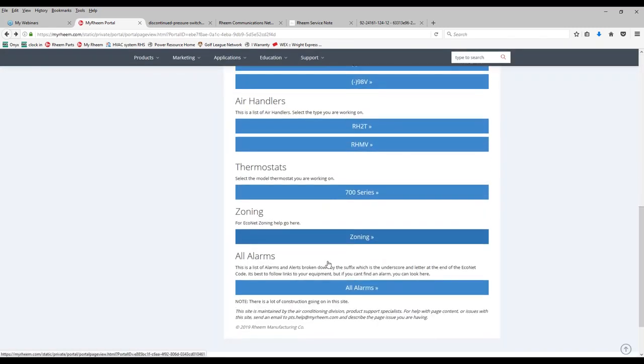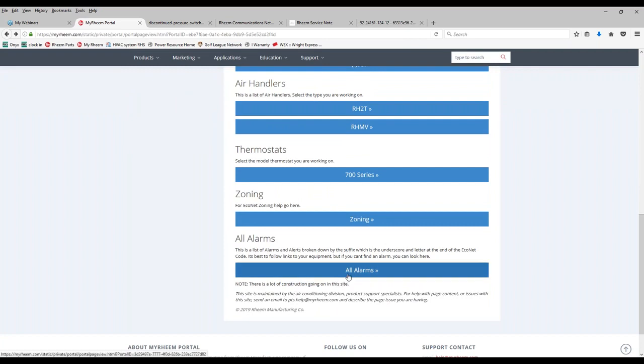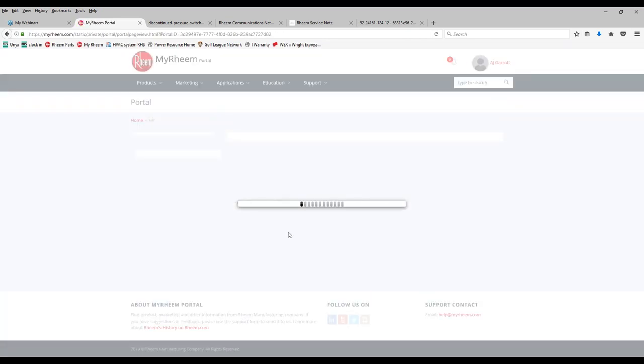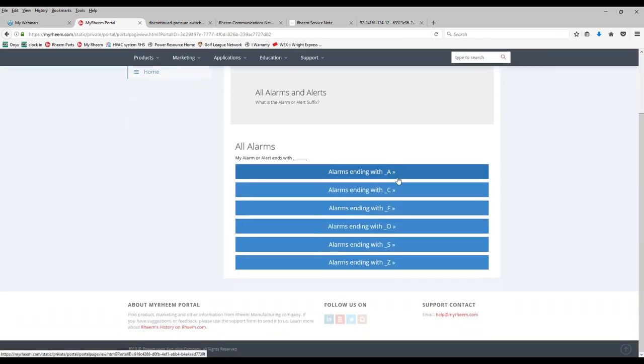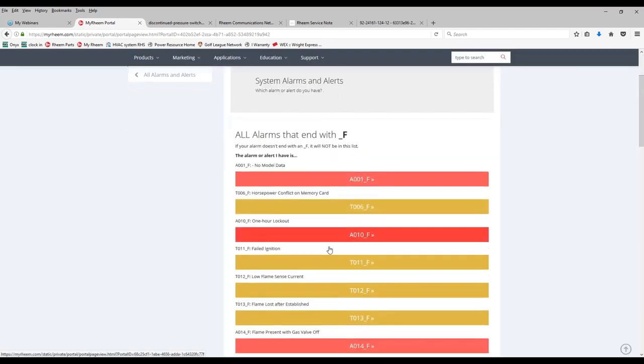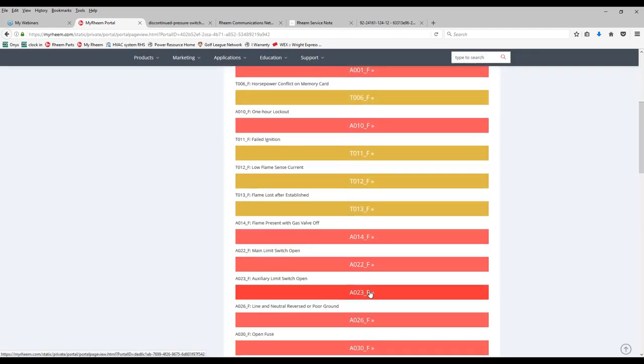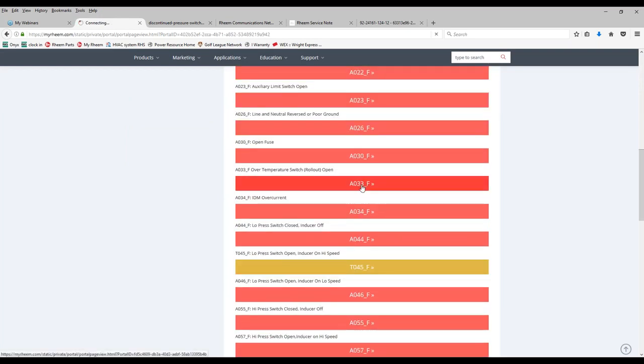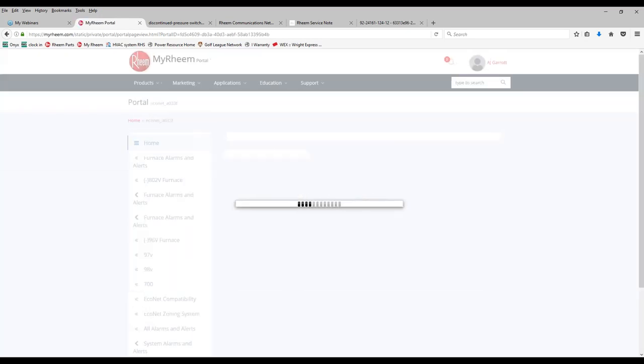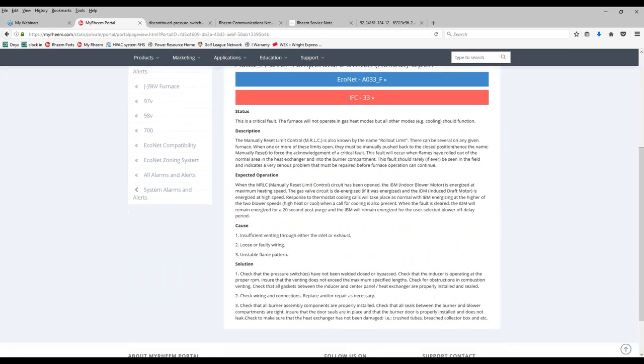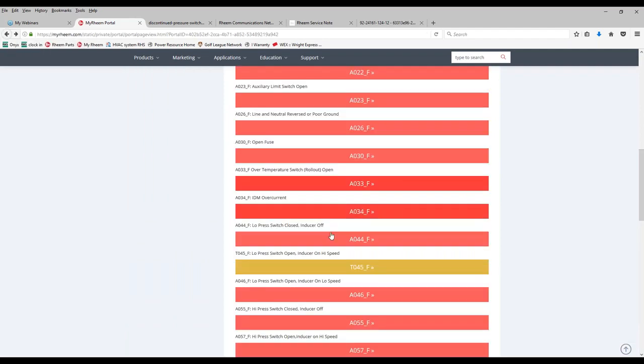The other thing I want to point out is coming down is they have all alarms. When you click all alarms, it's going to ask you, what does your alarm end with? Now, you may not know that. What do you mean, what does my alarm end with? We looked at the gas furnace one. It ended with an _F. That was for furnaces. You can click on that and then go down through all the alarms that work with the gas furnaces. So again, we could go to 33, which is an over temperature switch. So a rollout switch is open. And it will give us information on how to troubleshoot and what causes those to open up, what to look for. I'm going to go back.